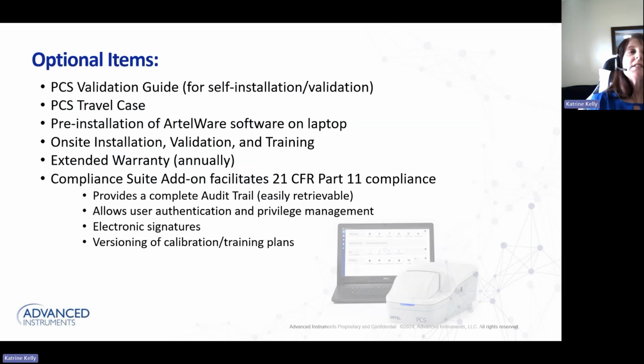So in addition to the standard PCS package, you can also add on additional features and hardware. We offer a system validation, installation, and training package to validate and do an IQ, OQ of the system on site. If your system is going to be shared across multiple facilities, you may want to consider purchasing a travel case. It is a hard side case with wheels and a handle. If you would prefer to have the software pre-installed on an Artel laptop, we can certainly provide that service to you prior to shipping, or we can come on site and perform that complete installation IQ, OQ that I mentioned.